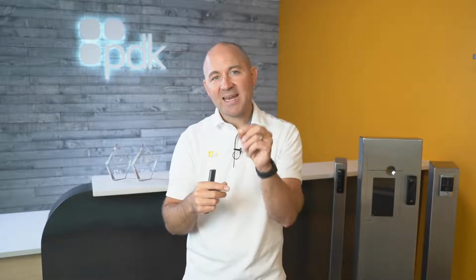But if you look at data 1 and data 0, coming back to that, they don't toggle between each other to provide data 1 and 0 to the controller. They're actually toggling between the ground that's connected to the controller. So you've got your positive and your negative. If I have the negative connected to the controller, it's going to toggle my 1 between negative and my 0 between negative.